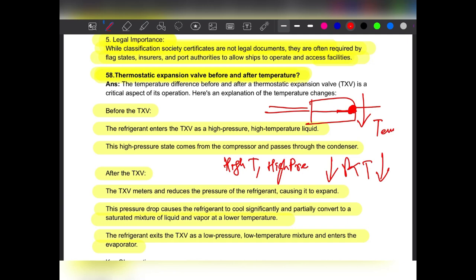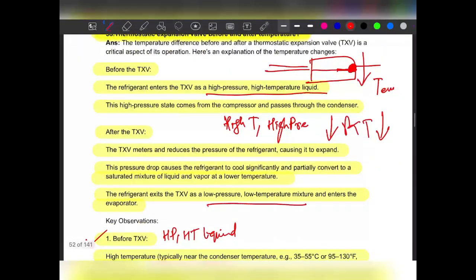TXV nozzles. So basically the main purpose is it senses the temperature from the chamber. If the temperature is not according to the set point, then it opens the valve, and the refrigerant will start flowing through this TXV, and this TXV will reduce the pressure, and due to this reduced pressure, the high pressure, high temperature liquid will convert into low pressure, low temperature liquid, which is basically in liquid form, and when it goes to the evaporator, it will directly vaporize, it will directly absorb heat from the hot atmosphere at the evaporator.